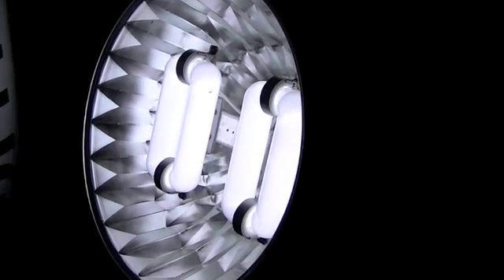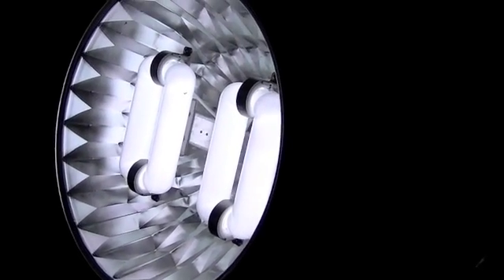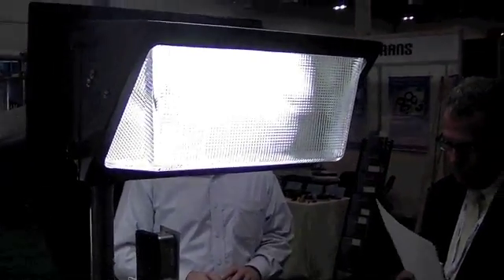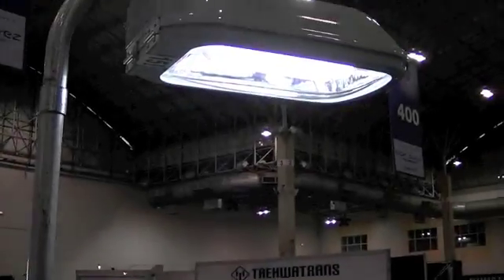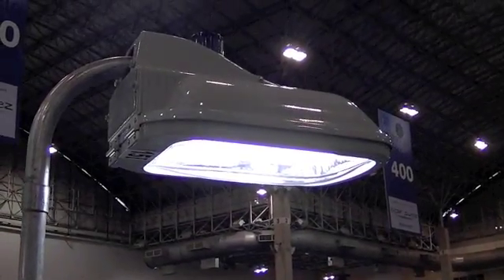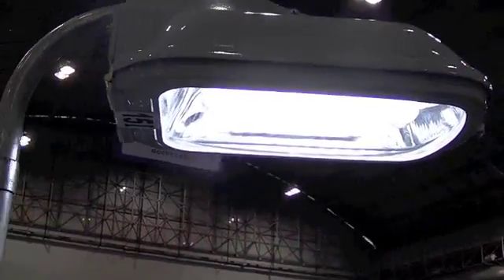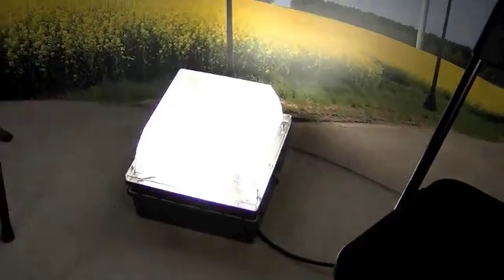So here you have a long life naturally, because you don't have the little electrodes wearing out. If you notice on fluorescence, where it grays on the end — that's basically the lamp wearing out. Every time you turn it on and off, you take a little chunk out of the life of a fluorescent, because you're wearing out the electrodes. All these fixtures use induction lights that last 10 times longer and use less energy. They do use mercury and are breakable, but they are a cheaper alternative to LEDs.